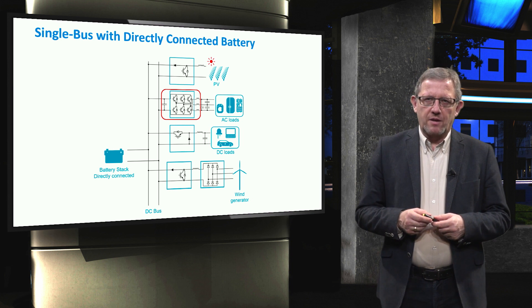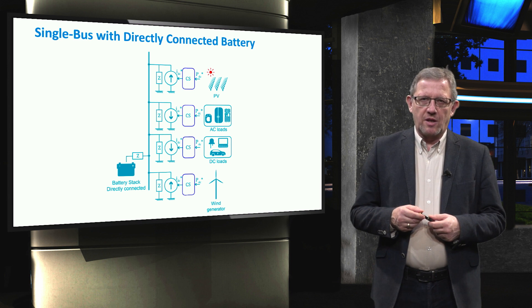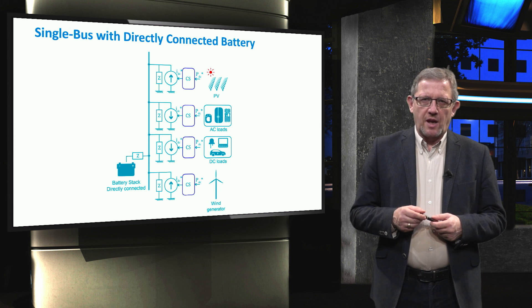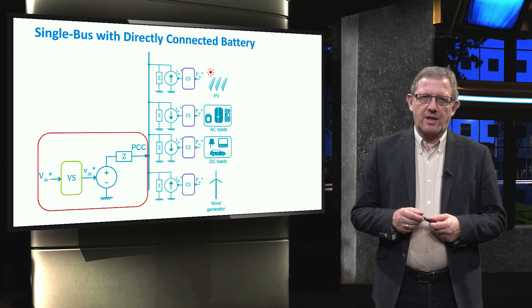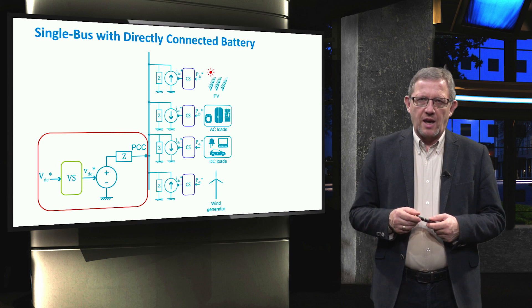Which element is grid forming — guarding the DC bus voltage — and which element is grid feeding? The grid forming and grid feeding representation of the same single bus with directly connected battery is shown in this slide. The battery is seen as a large capacitor, represented as a grid forming voltage source in series with an impedance. Other renewable sources like photovoltaic solar and wind, which have limited control over their input sources, are modeled as grid feeding current source-based units in parallel with an impedance. Both DC and AC loads can also be modeled as grid feeding. In this representation, the DC link voltage is set according to the state of charge of the battery, which is related to the open circuit voltage of the battery stack.